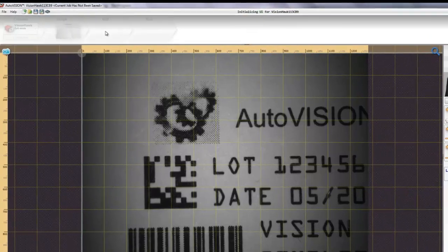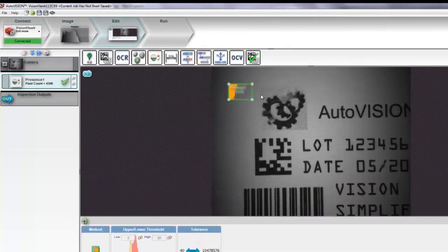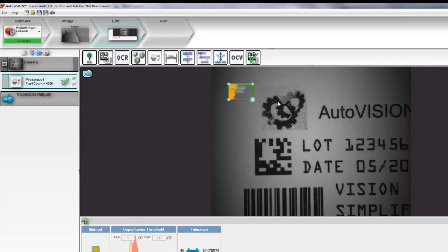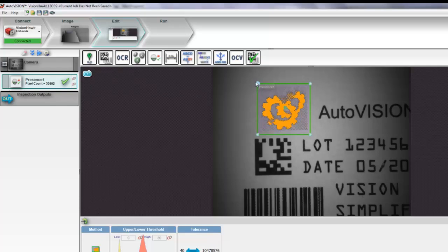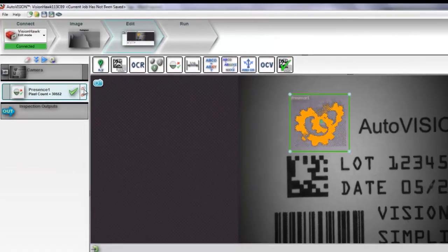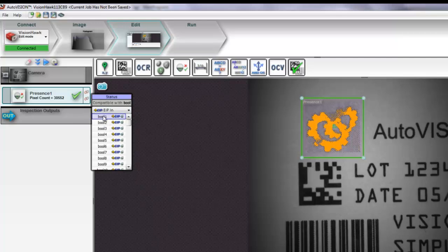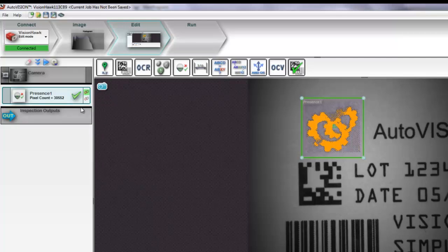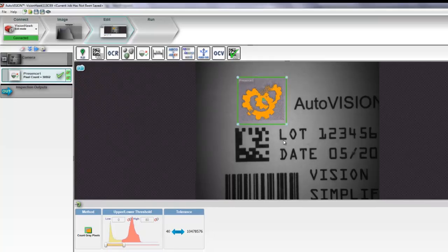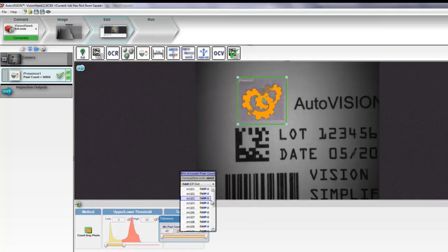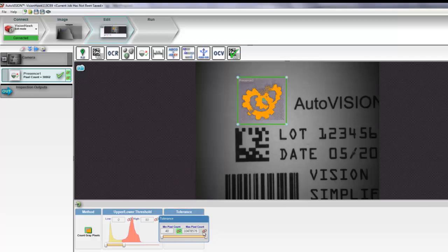The first tool that we will insert in this tutorial is the Presence Absence tool. We can publish the results of this tool to the PLC through Microscan link, and at the same time set the tolerance levels from the PLC back again through Microscan link. In order to take the two outputs, click the link and select Boolean 101 for the status flags. Click on the output of the tool and select Long 1 for the output. On the input side, we can take the tolerance and link it to Long 101 for the minimum pixel count and Long 102 for the maximum pixel count.